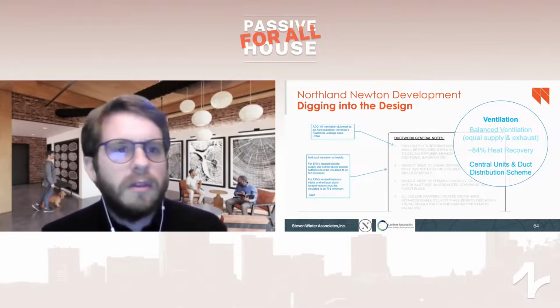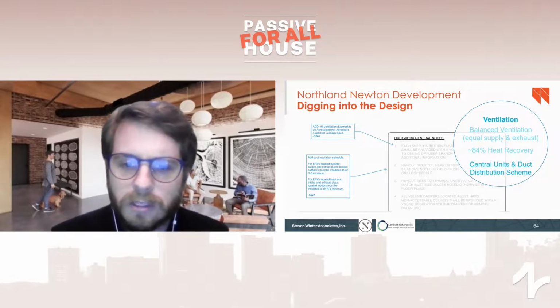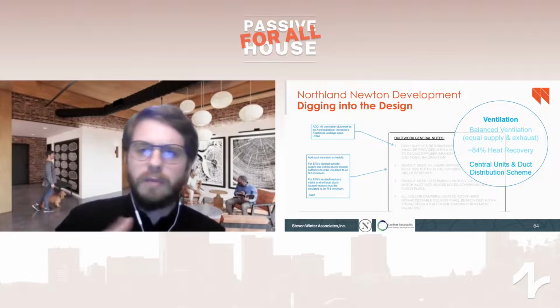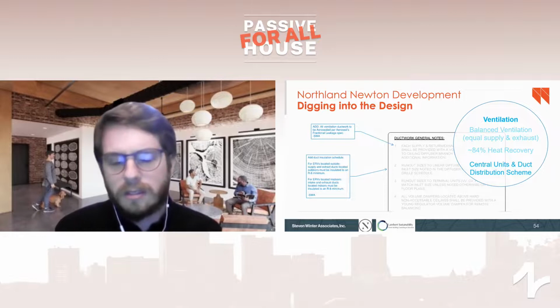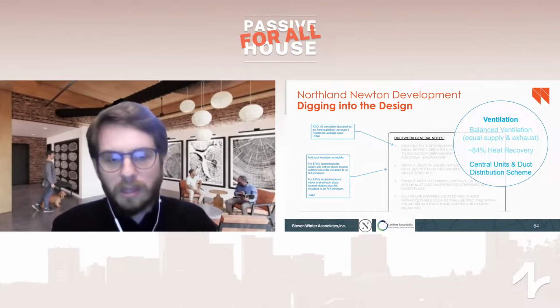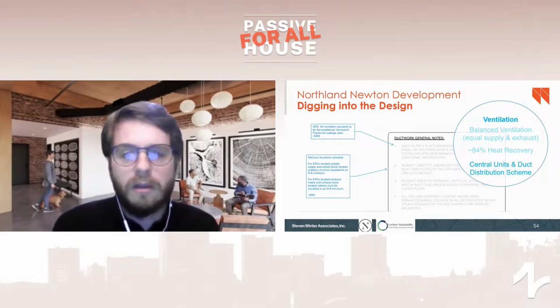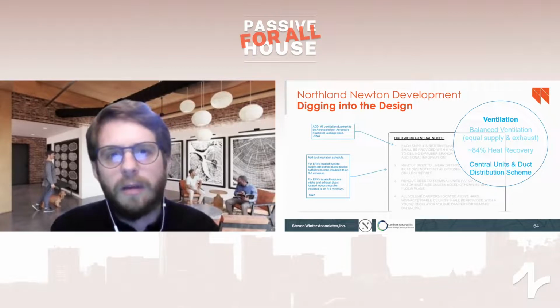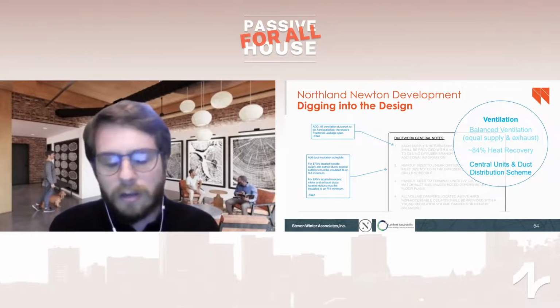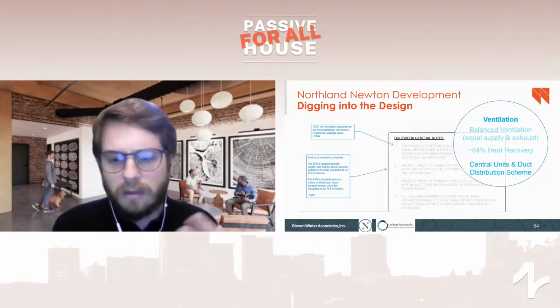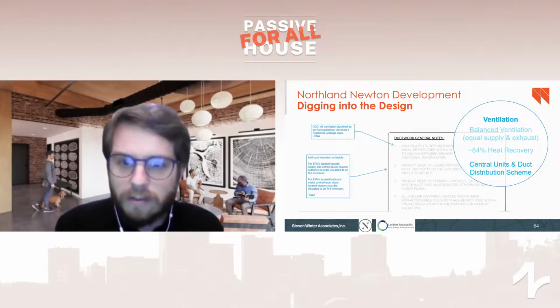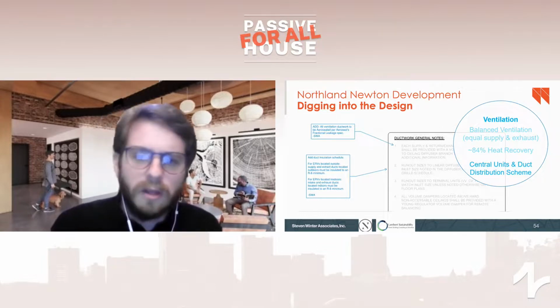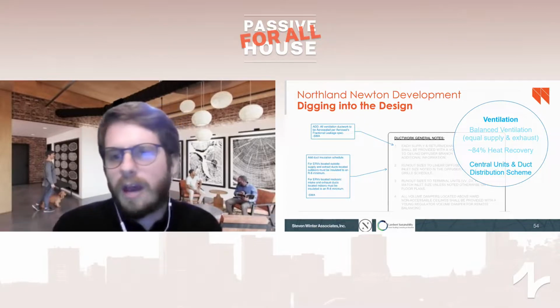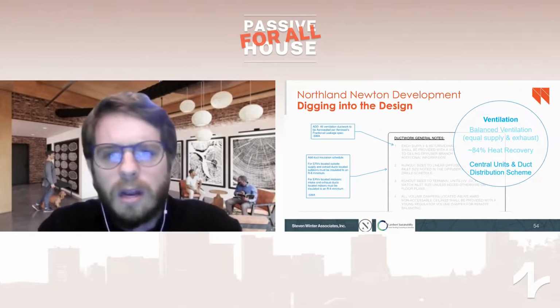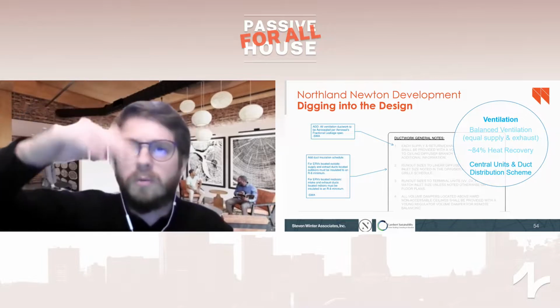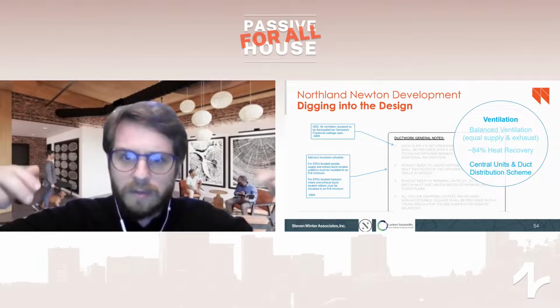So on the ductwork system itself, one of the biggest things with centralized ductwork, especially in residential buildings, is you have a lot of kind of spaghetti network of ductwork, a lot of horizontal turns, a lot of joints. That's going to be where air can leak out, and that's where the typical hand sealing of ductwork can sometimes not be fully effective. So what we do is we specify that all of the ductwork needs to have gone through the aeroseal process, which is basically injecting a duct sealant, if you will, into the inside of the ductwork, pressurizing the duct, and it fills any holes and gaps, I believe, a quarter of an inch or smaller. And it really helps with those hard to reach areas, particularly the tops of ductwork, where we've seen problems and challenges getting good seals.